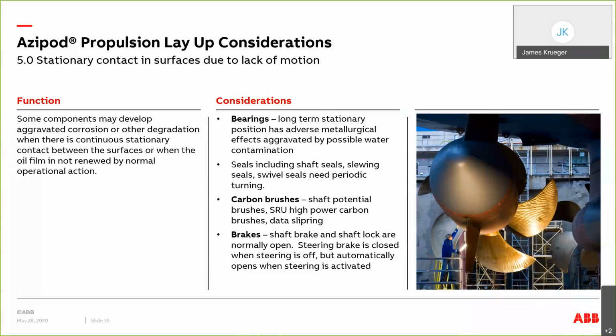A couple of other equipments include the carbon brushes. The carbon brushes, of course, need to be moved periodically so they don't get stuck to the surfaces with which they meet. And lastly, items such as brakes may get stuck in the open or closed position if they've been in those positions for quite some time. As with any mechanical device, corrosion can quickly ensue, and again, if it's not been exercised, that leads to failure rather quickly. Next slide.